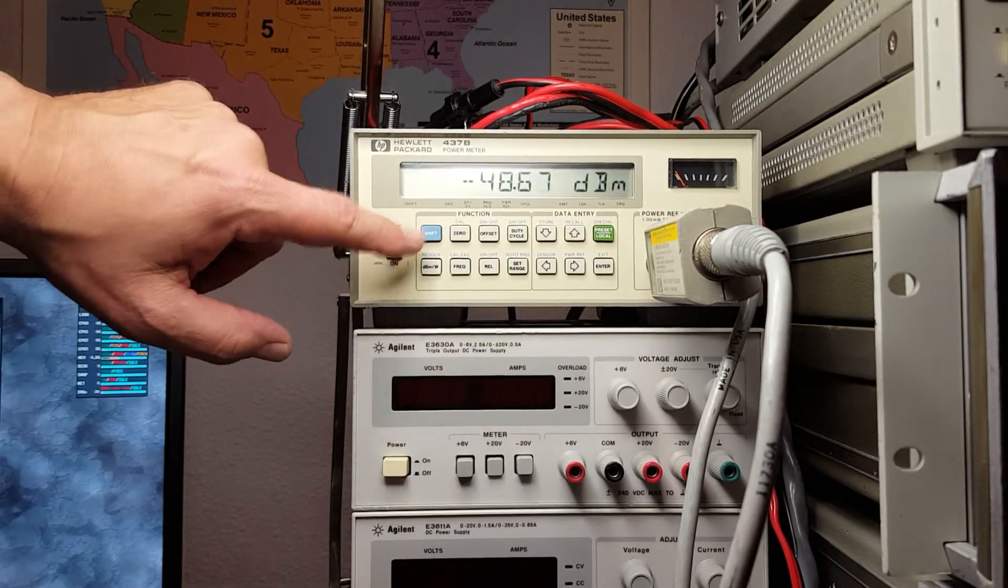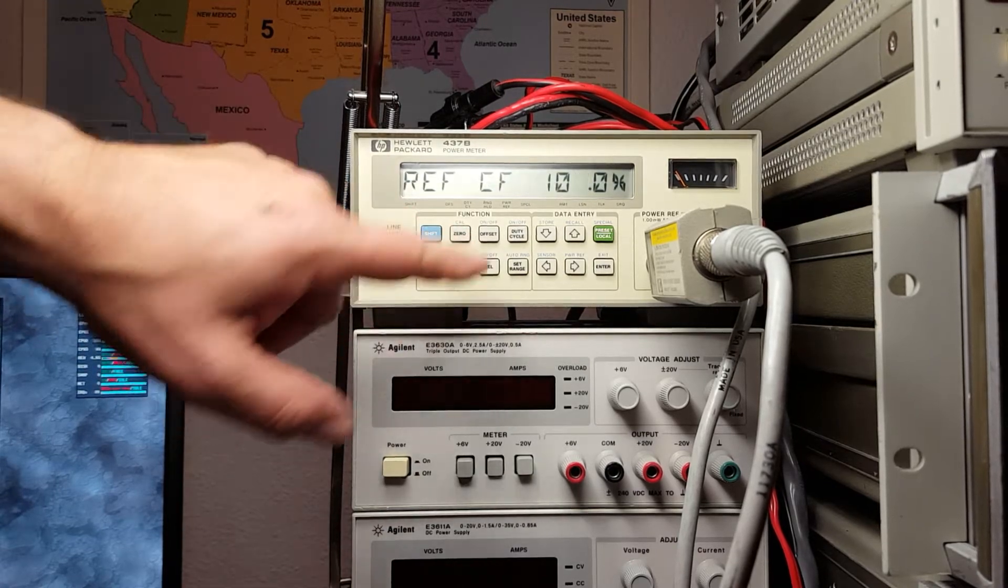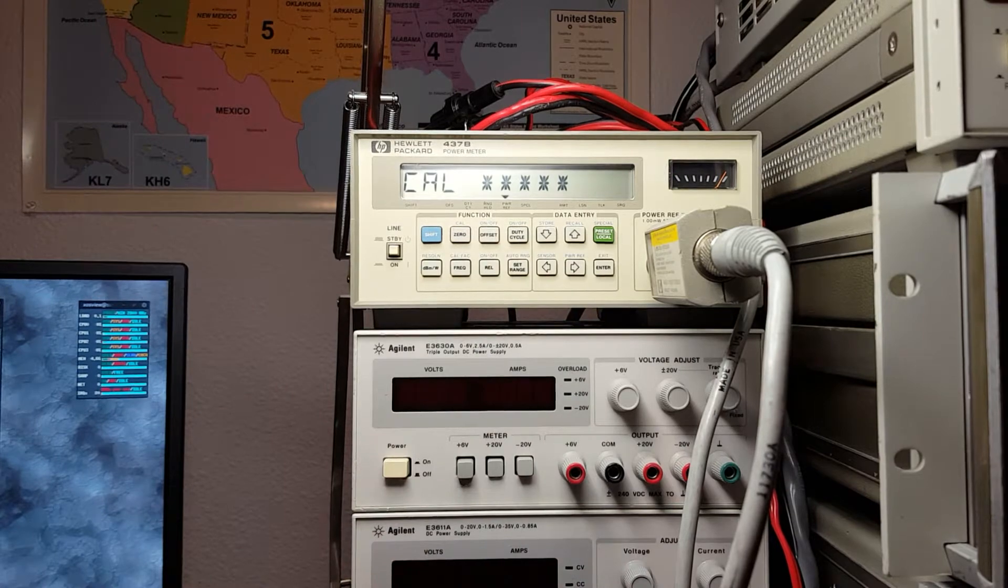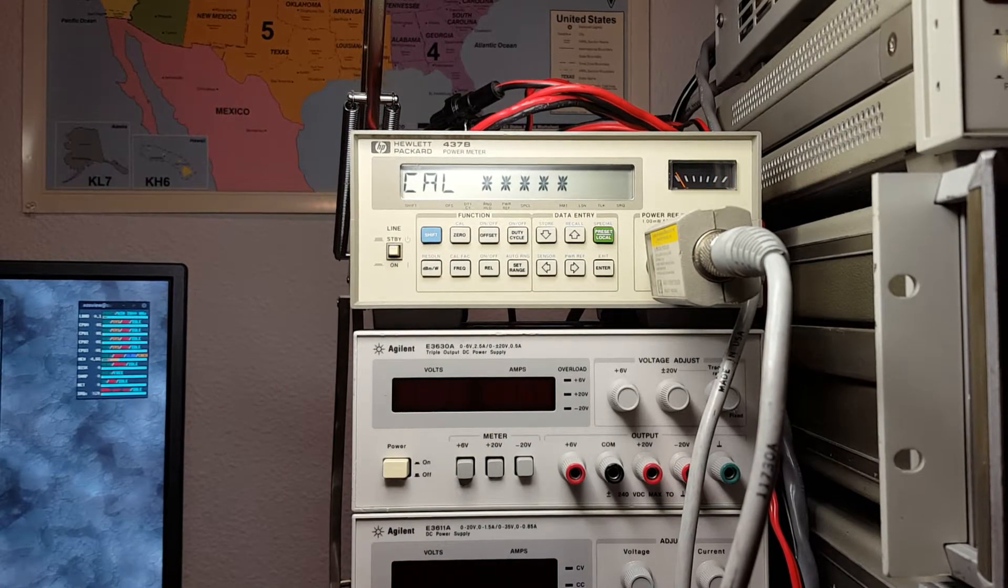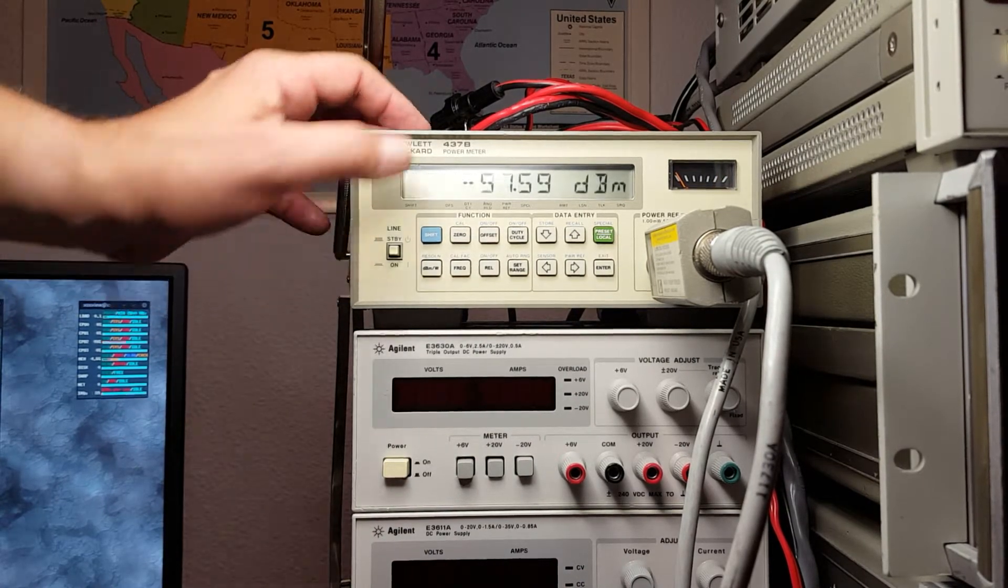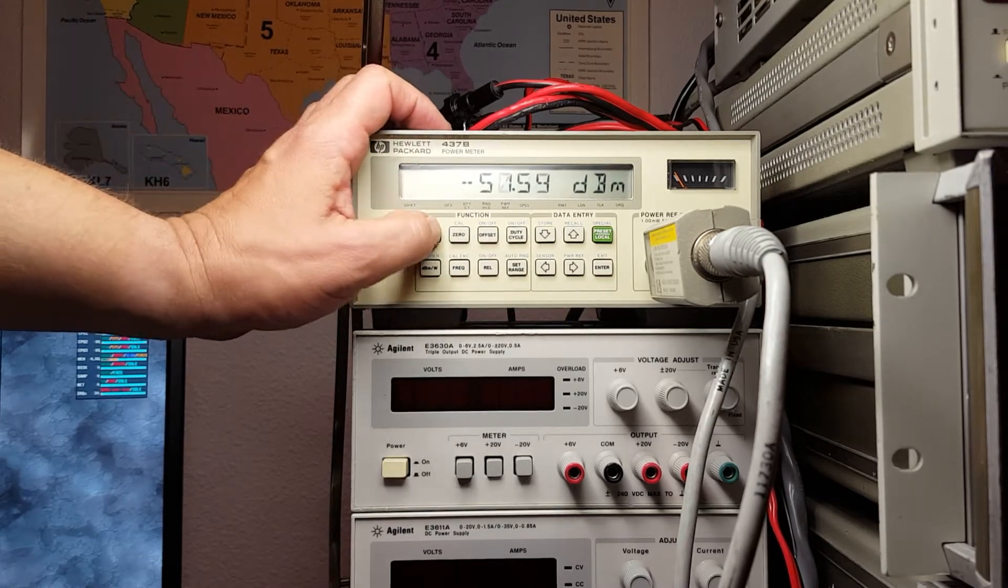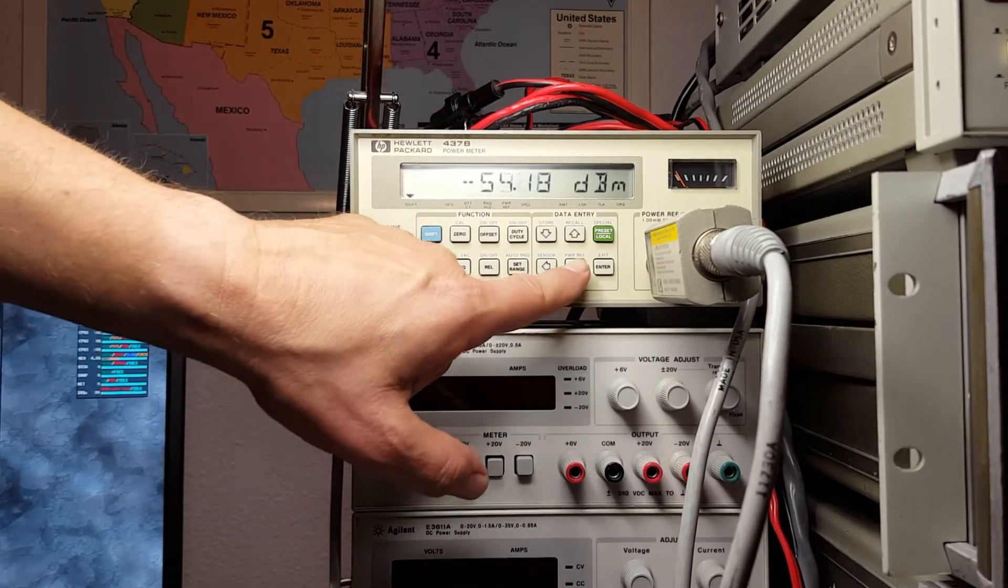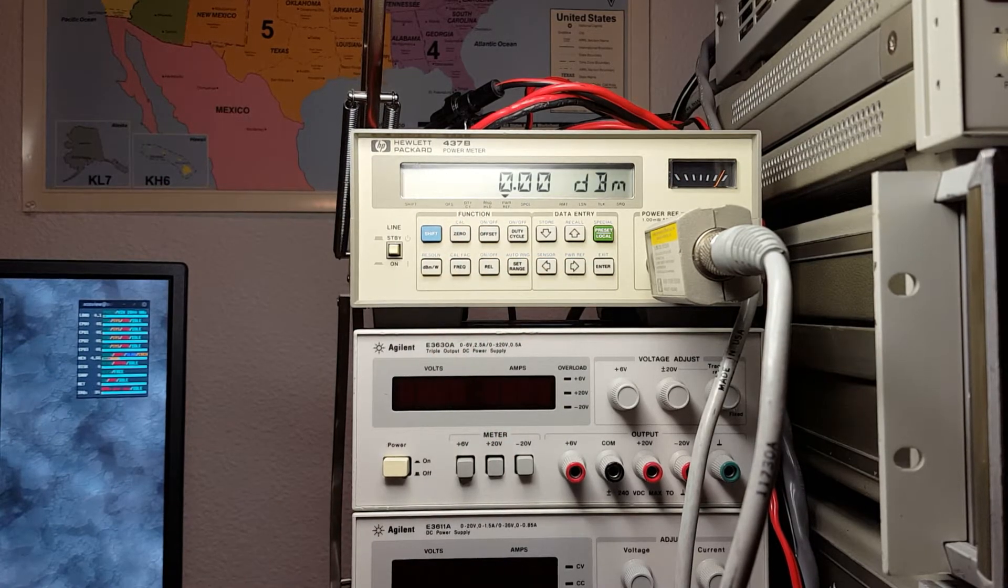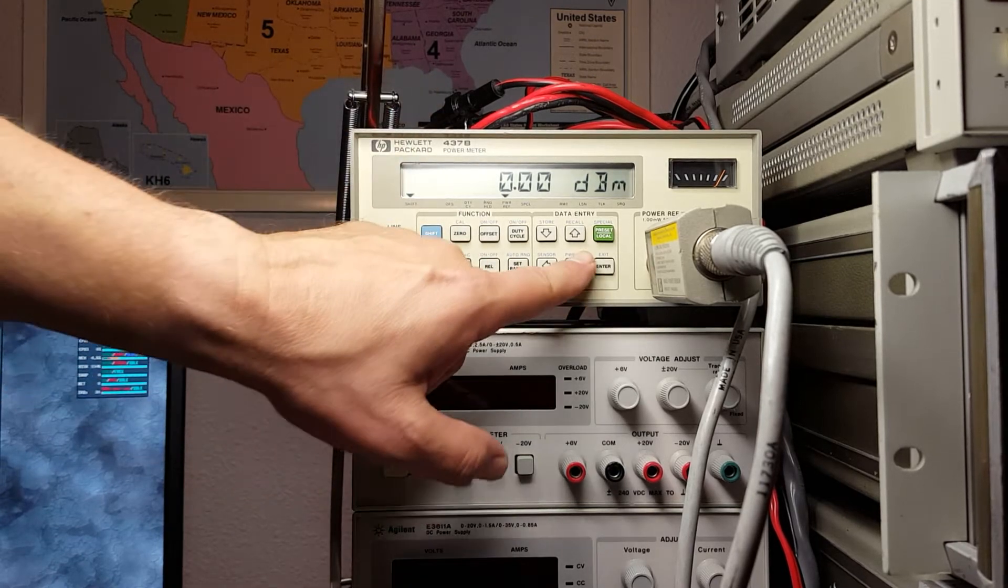Once that's done, we set the calibration factor to 100 percent, which is where it's at. Now we calibrate the element and select 100 percent. It's done. To verify that the calibration took place, we shift and turn the reference on, and it is at zero dBm, just the way it should be.